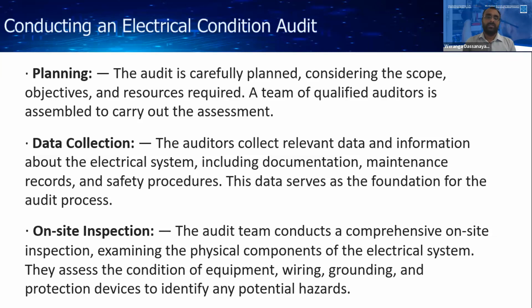When you go for a condition audit, you cannot just look and say whether the system is healthy. For that, you may require measuring or testing instruments, so you have to gather them, and a qualified team, prior to starting. Then data collection. That means you go to the premises and do a visual inspection, and you check the available documents, such as whether drawings are available. You can also meet the technical person there and ask what faults have been identified in the system. You have to get some idea about the system from a technically qualified person who uses it.